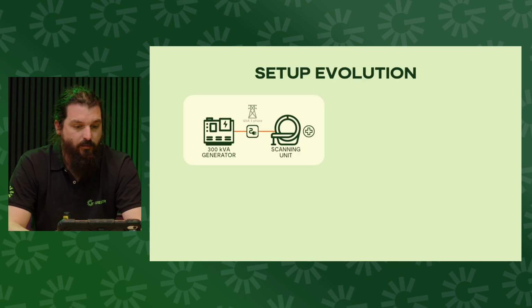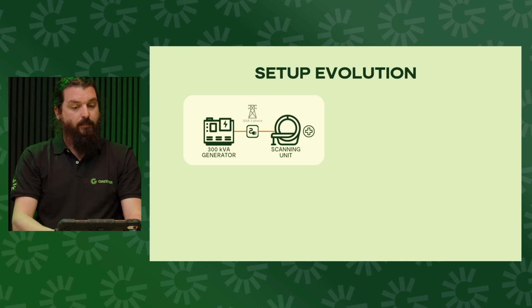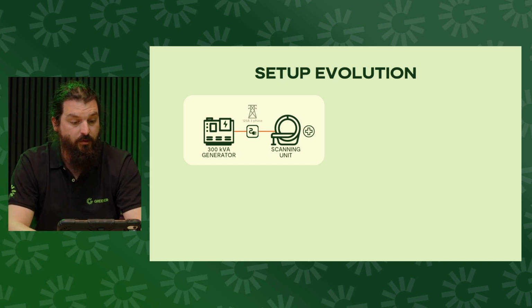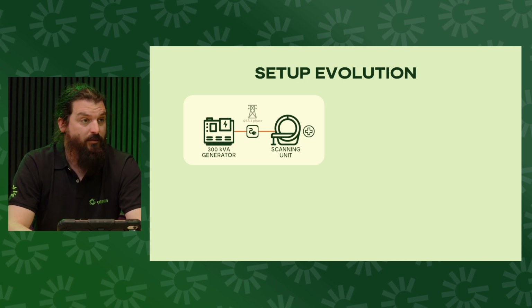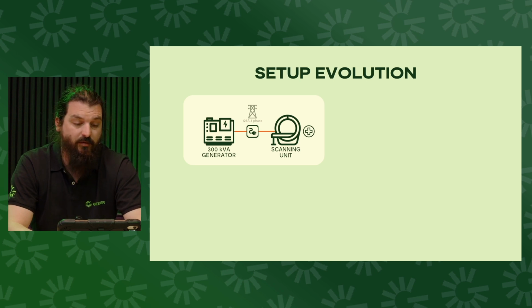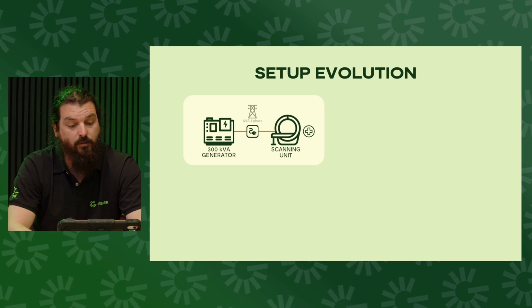When we first encountered this setup, there was a 300 kVA generator running for the entirety of the open hours when the scanners were supposed to be available, with a lot of stand-down time and being very inefficient. There was also a 125 amp three-phase connection available, but this was not powerful enough to actually support the inrush of the system.